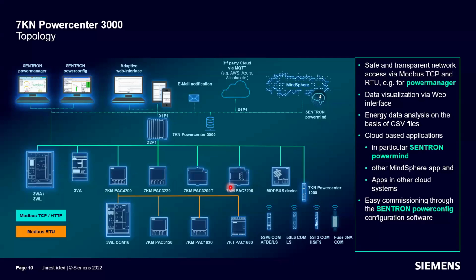Not only that, but I can also communicate with downstream devices in the final distribution board, like the MCB and AFDD, connected to give information or diagnosis on whether it has tripped, on what fault, and the timestamp of the event. To go further, I can also communicate with the fuse through this device to Power Center 3000 or via the gateway.